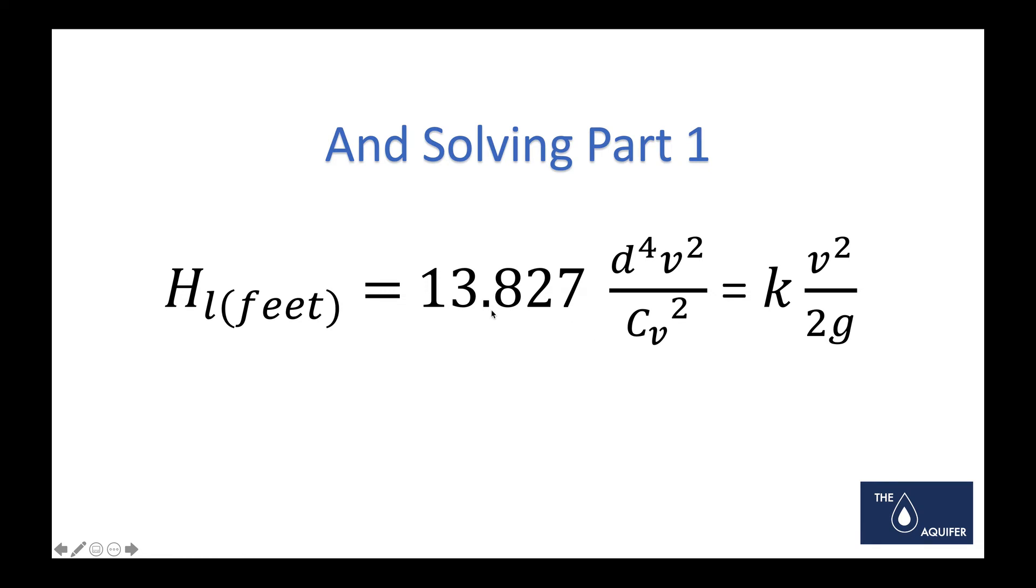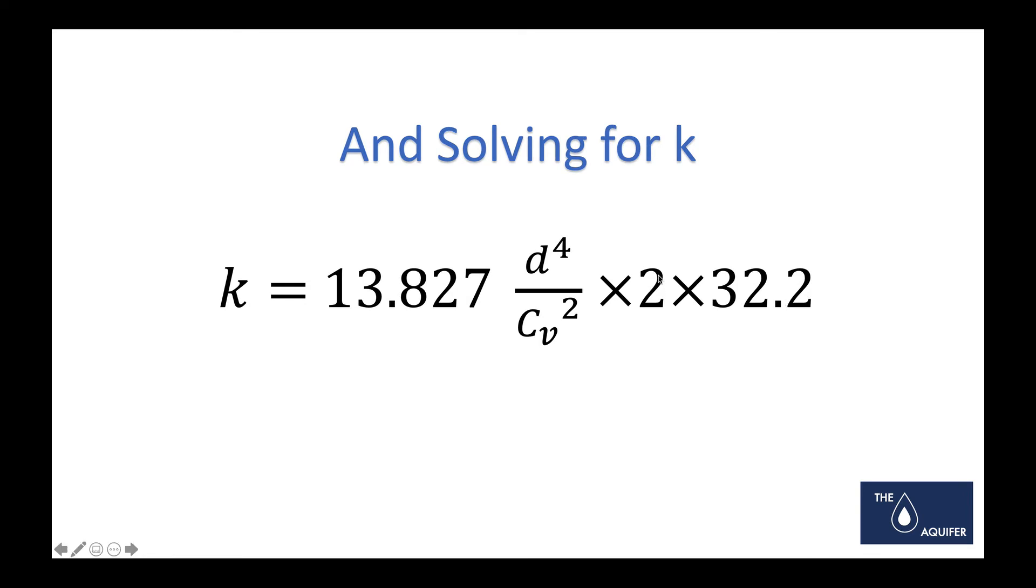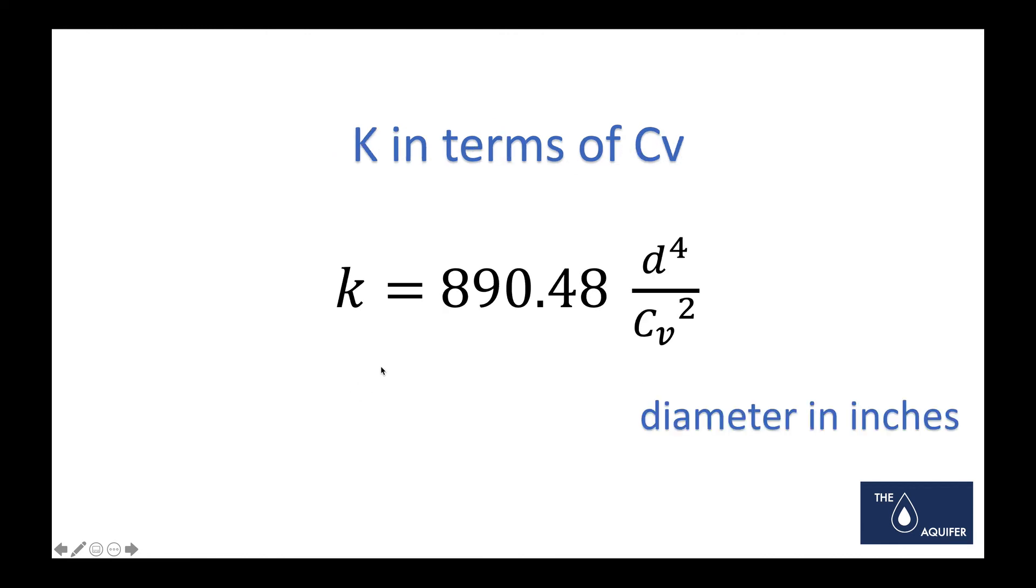Simplifying this, we know that the head loss is also equal to K times V squared over 2g—Darcy-Weisbach. So then we can do another reduction of this equation, flipping the gravity constant and the two to the right side of the equation and solving for K. We get that the K value is equal to 890.48 times the diameter to the fourth power in inches divided by the Cv squared.